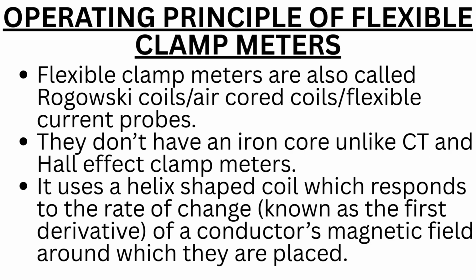Now let us look at the operating principle of flexible clamp meters. But first, what is a flexible clamp meter? Flexible clamp meters are also called Rogowski coils or air-cored coils or flexible current probes. They don't have an iron core unlike CT and Hall effect clamp meters. It uses a helix-shaped coil which responds to the rate of change, known as the first derivative, of a conductor's magnetic field around which they are placed.